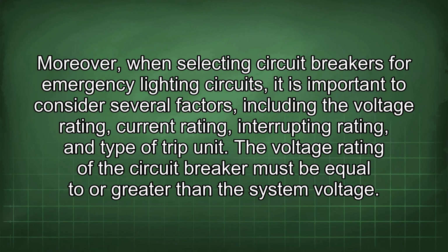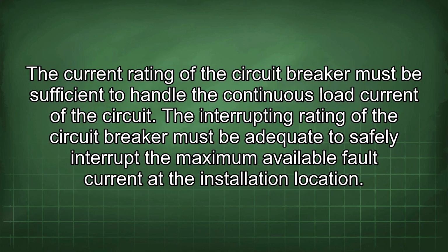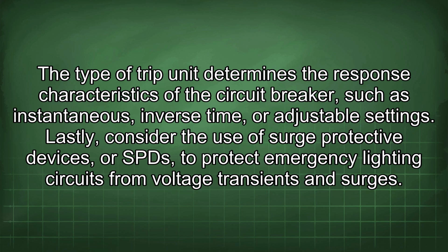Moreover, when selecting circuit breakers for emergency lighting circuits, it is important to consider several factors, including the voltage rating, current rating, interrupting rating, and type of trip unit. The voltage rating of the circuit breaker must be equal to or greater than the system voltage. The current rating of the circuit breaker must be sufficient to handle the continuous load current of the circuit. The interrupting rating of the circuit breaker must be adequate to safely interrupt the maximum available fault current at the installation location. The type of trip unit determines the response characteristics of the circuit breaker, such as instantaneous, inverse time, or adjustable settings.